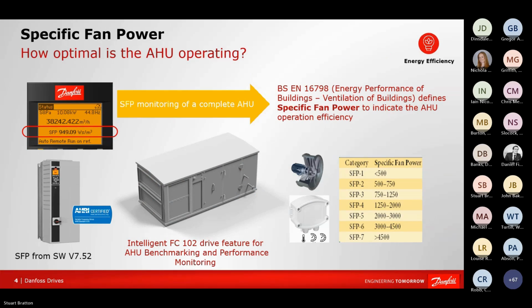So, although I'm going to talk about what we call CBM in Danfoss, condition-based monitoring, which is an add-on, let's say, to a standard drive, we actually have some condition monitoring that's part of some of the drive's standard functionality. So if you're sat in an office today, sweltering, maybe this is particularly relevant. Our FC102 HVAC drive, for example, has the ability to monitor the amount of power or energy that's required to produce a specific flow or volume of airflow.